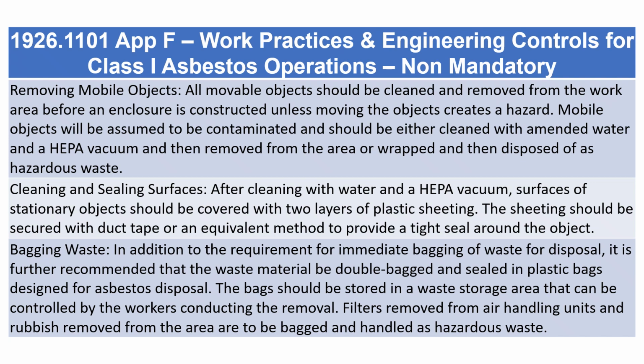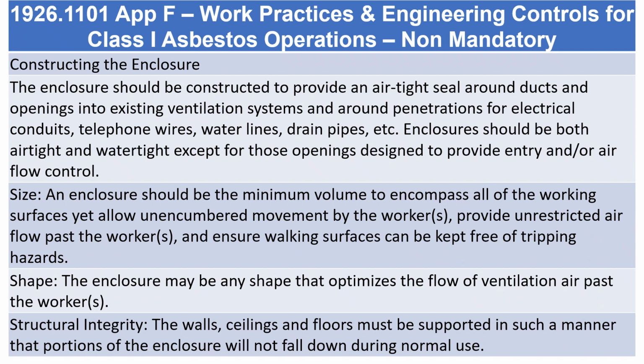Filters removed from air handling units and rubbish removed from the area are to be bagged and handled as hazardous waste. Constructing the enclosure. The enclosure should be constructed to provide an airtight seal around ducts and openings into existing ventilation systems and around penetrations for electrical conduits, telephone wires, water lines, drain pipes, etc. Enclosures should be both airtight and watertight except for those openings designed to provide entry and/or airflow control.